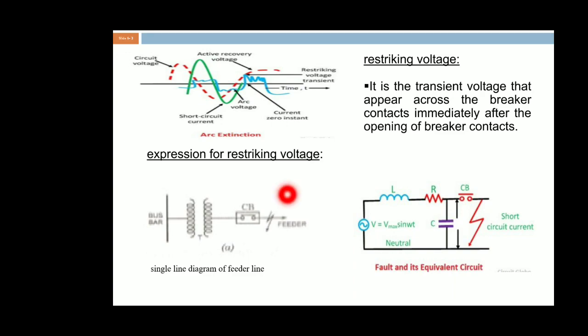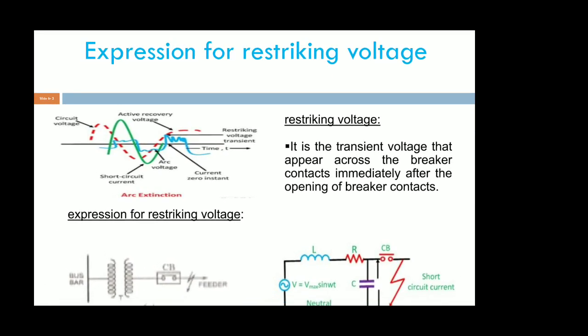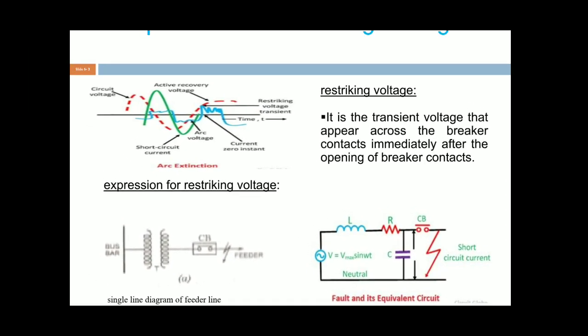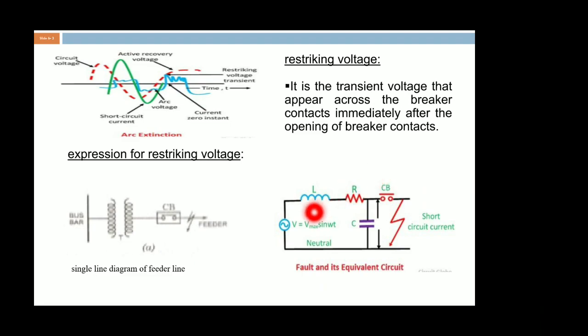For every current zero interruption, the arc may be extinguished, but it does not normalize instantly. It may oscillate like this. At the starting of the oscillation, a voltage may appear. This voltage may be calculated by using the equivalent circuit.